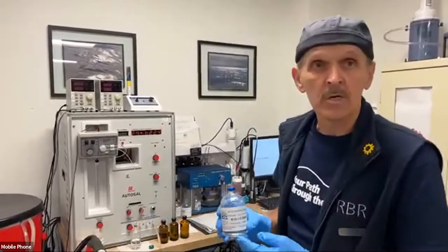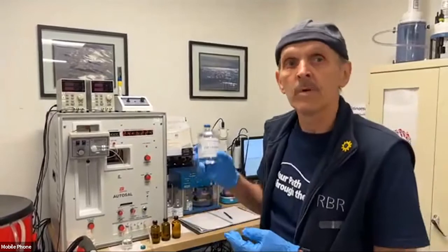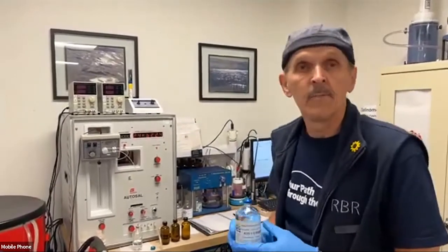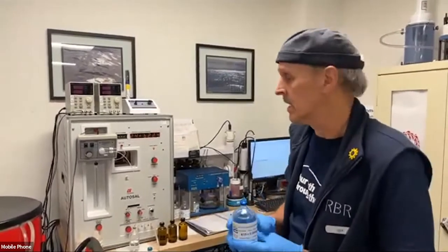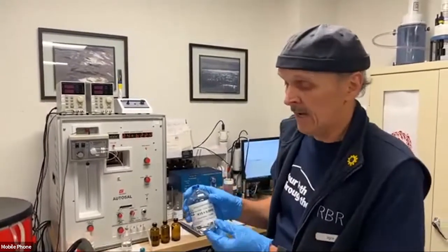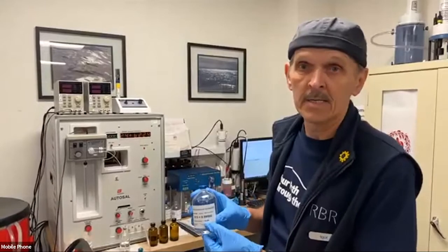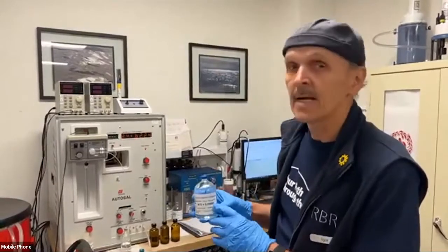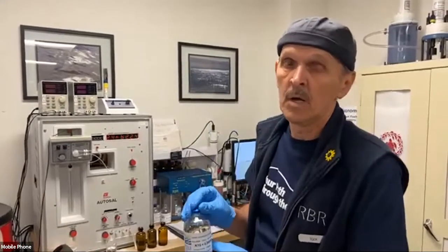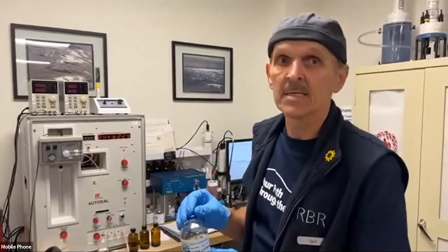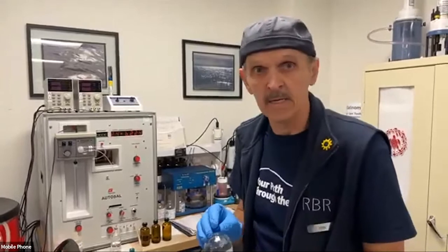It's actually natural Atlantic seawater, which was taken in the Gulf of Biscay at depths of about 100 meters, very well filtered and diluted to very close to the certified salinity. After that, it's calibrated against potassium chloride according to the practical salinity scale, which has been established in oceanography since 1978.